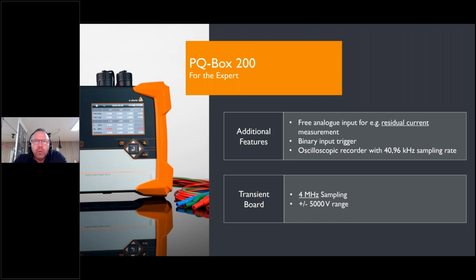With the PQ-Box 200, we deliver more possibilities to the user. In addition to the four voltage and four current inputs, we have a binary input. For example, you have a big power plant and sometimes you have some disturbances. Either you can set all the triggers, like overvoltage or dips, or the easier way is to look at which voltage you are losing or which voltage is coming during a disturbance, and you put this voltage on the binary input. It could be any AC or DC voltage you connect to the binary input. And we can start and stop the disturbance recorder directly from this signal.